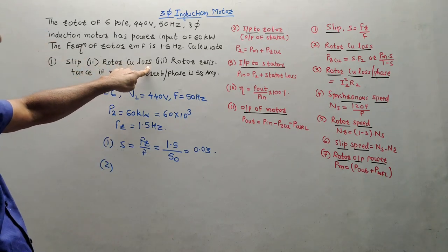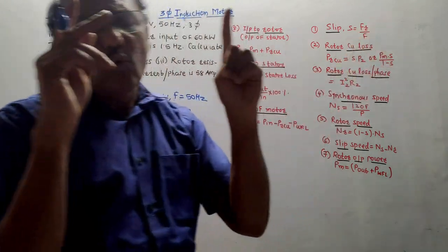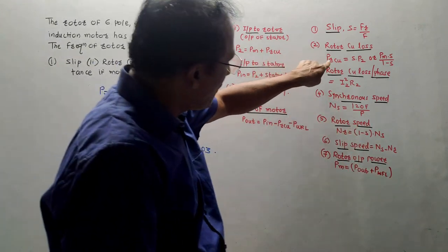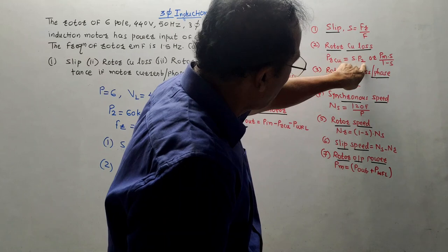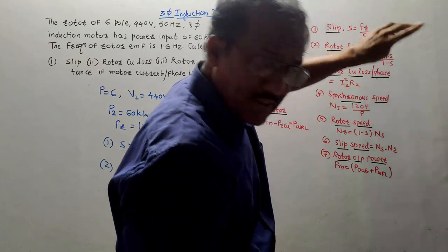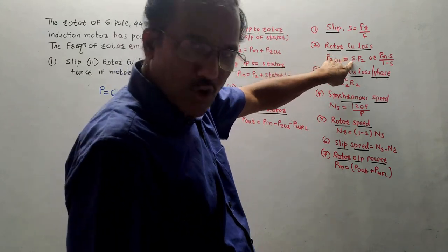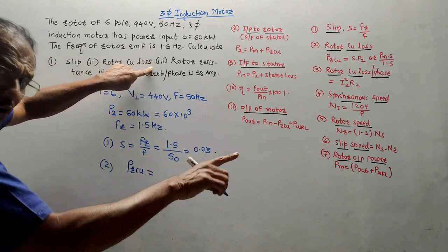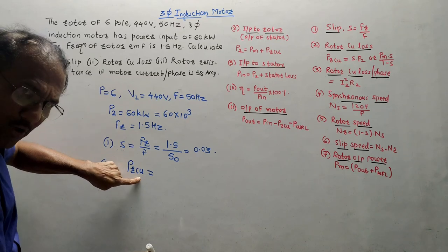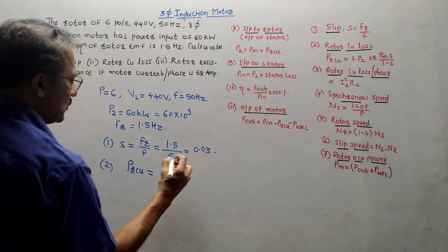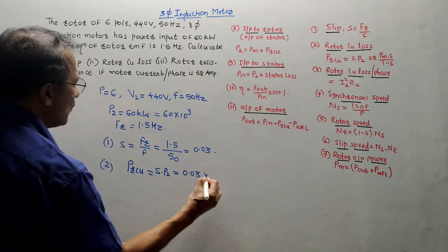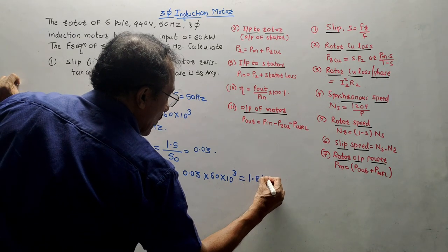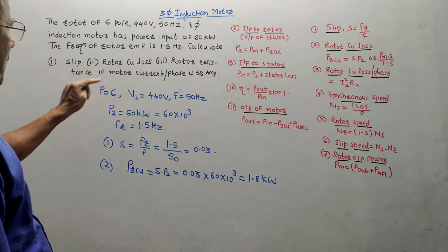Second part: rotor copper losses. Rotor copper losses are given by the second formula. There are two major types of losses in this system: first is the copper losses and second is the windage and frictional losses. For copper losses, we have two formulae: one is S × P2 and the second is PM × S / (1 − S). PM is not given in the question, so I use the first formula. Rotor copper loss, PRCU = S × P2 = 0.03 × 60 × 10³ = 1.8 kilowatt.